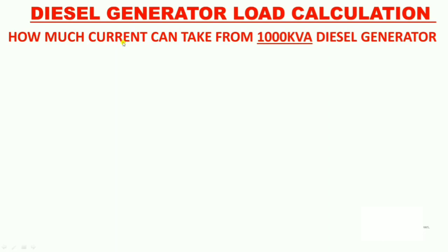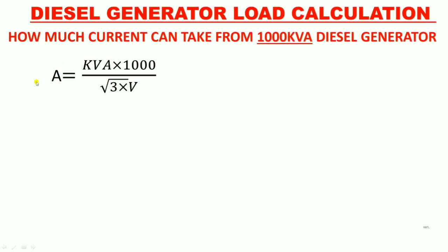First, understand which formula is used for this calculation. This formula is generally used for calculating the full load current of a diesel generator. In this formula, A stands for full load current in amperes, kVA is for the diesel generator rating, √3 is used for three-phase supply, and voltage is the voltage generated by the diesel generator.